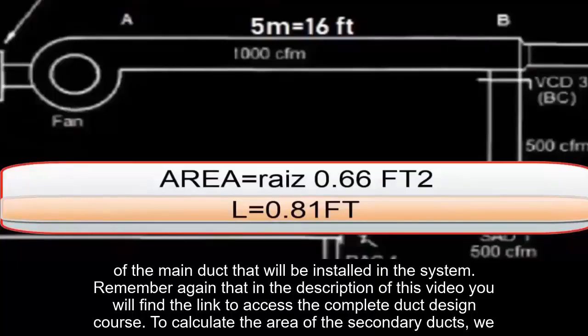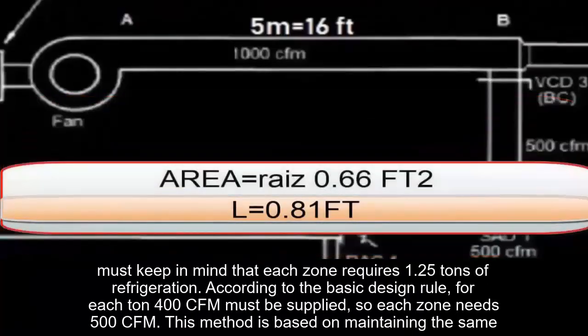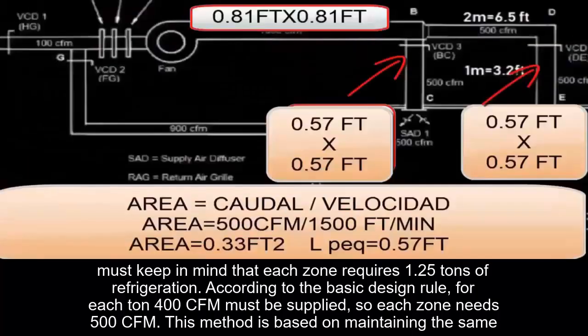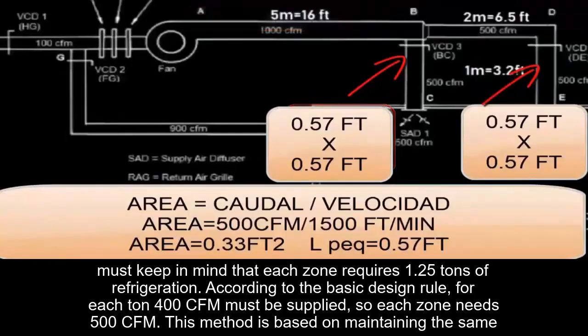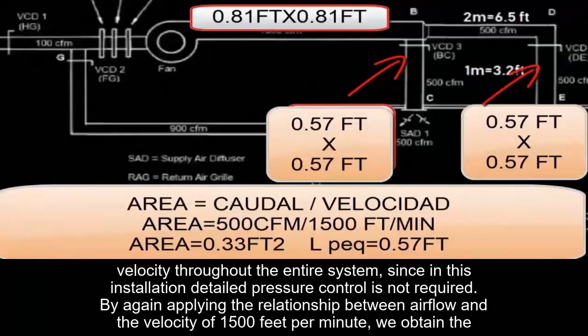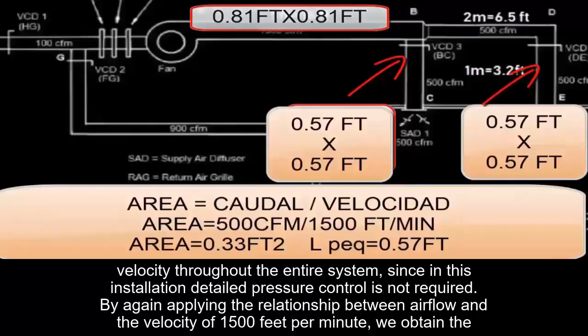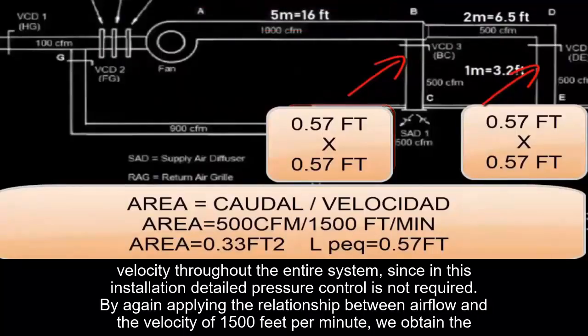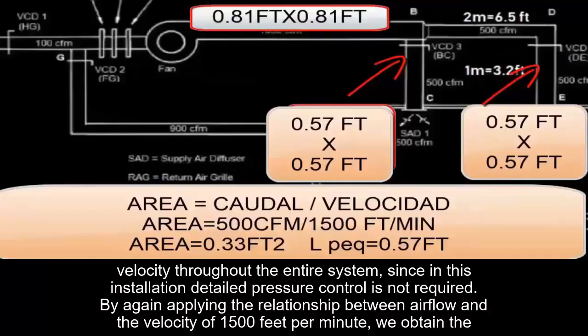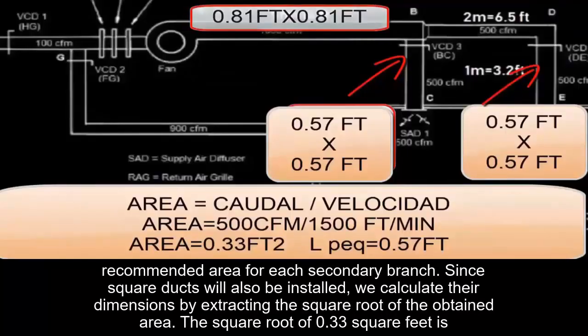To calculate the secondary ducts, we must keep in mind that each zone requires 1.25 tons of refrigeration. According to the basic design rule, for each ton 400 CFM must be supplied, so each zone needs 500 CFM. This method is based on maintaining the same velocity throughout the entire system, since in this installation, detailed pressure control is not required. By again applying the relationship between airflow and the velocity of 1,500 feet per minute, we obtain the recommended area for each secondary branch.